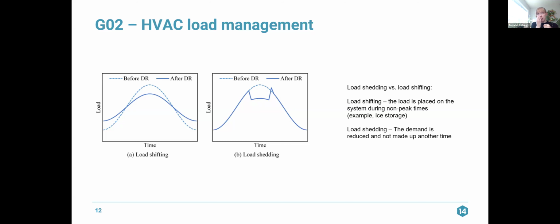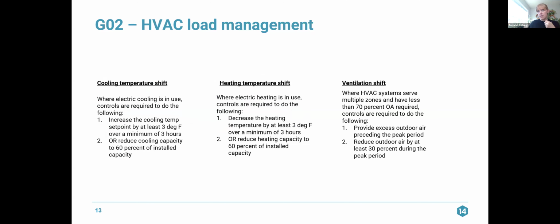So I just wanted to clarify this. Load shifting is when we are making ice at night, for example, and then using the ice to cool down our building, or heating all the domestic hot water in storage tanks to 180 degrees before we have a peak reduction event. Load shedding is when we're just traveling along as normal and we hear that we need to reduce our peak, and we drop our temperatures or reduce our light levels, something that automatically reduces the peak without future planning. So that's the description. That was my soapbox for the day.